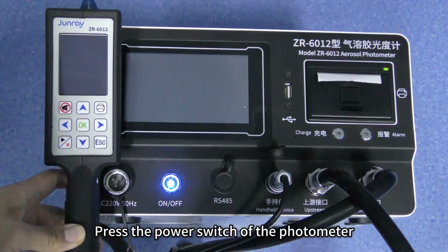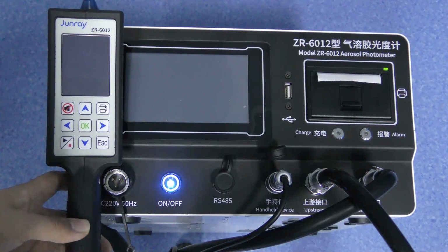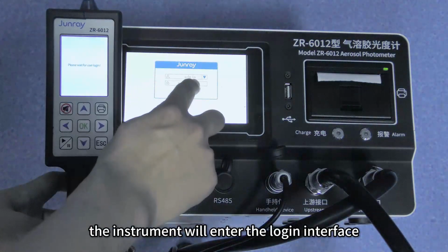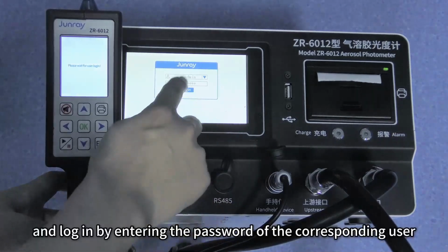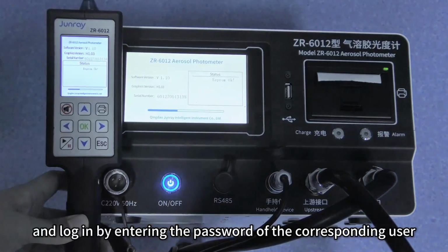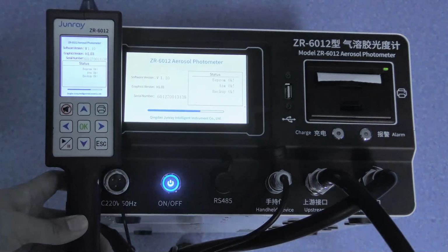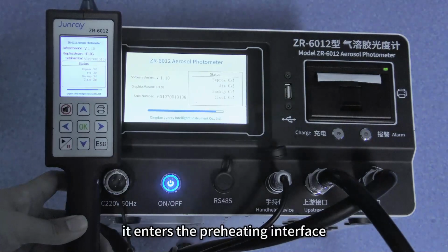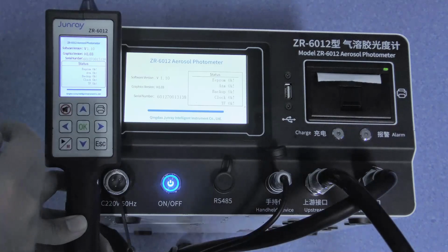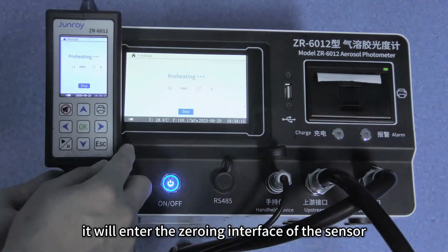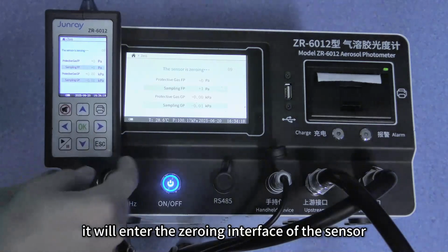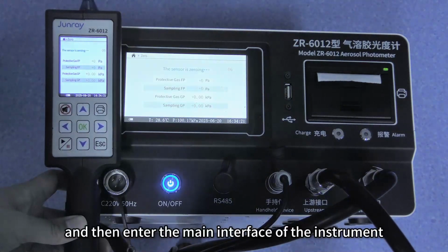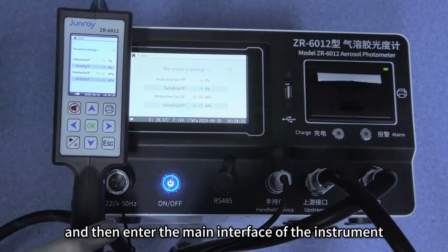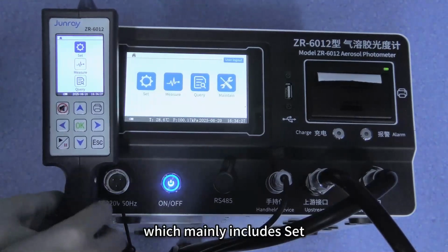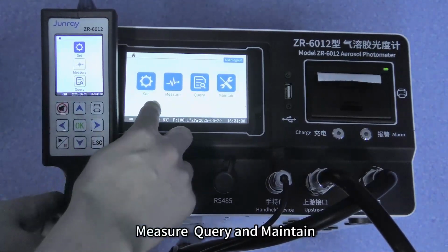Press the power switch of the photometer. The instrument will enter the login interface. We can select users here and log in by entering the password of the corresponding user. After the instrument self-checks, it enters the preheating interface. After the preheating, it will enter the zeroing interface of the sensor, and then enter the main interface of the instrument, which mainly includes set, measure, query and maintain.